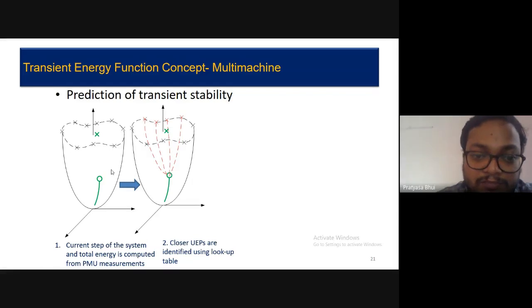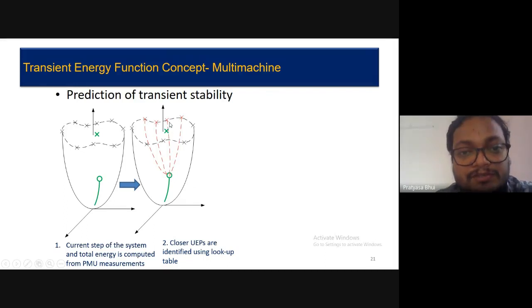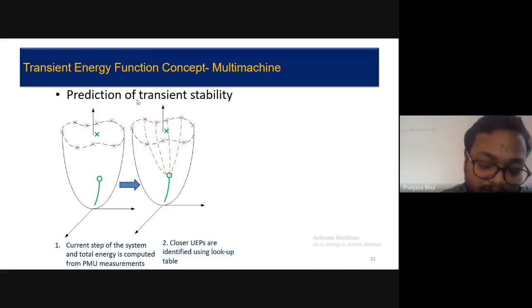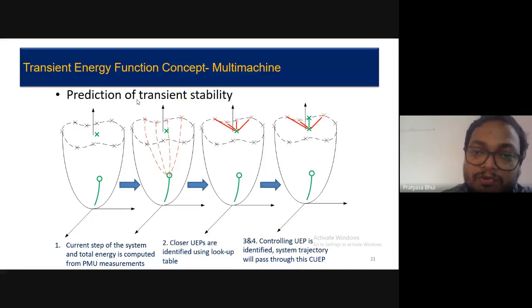Now, as I explained, the height of this bowl is not uniform. So before comparing the energy after fault clearing with the height of this bowl, we have to find out at which point the system trajectory will move. So based on the initial trajectory, we can predict that the system will move through these 4 points. Now each point corresponds to a group of generators that tend to become unstable. That may be one generator, that may be a group of generators. So each case represents one cross sign on the surface. So out of these 4, we have to identify which one is the closest unstable equilibrium point. Now the trajectory will move close to that point.